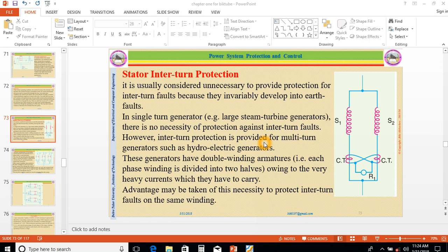For example, in a hydroelectric generator, each phase winding is divided into halves, two windings, owing to the very heavy current which they have to carry. So advantage may be taken of this necessity to protect against inter-turn faults on the same winding. You can see here in one winding there are double windings S1 and S2. So this is the two winding or double winding. Those two, S1 and S2, are in parallel.